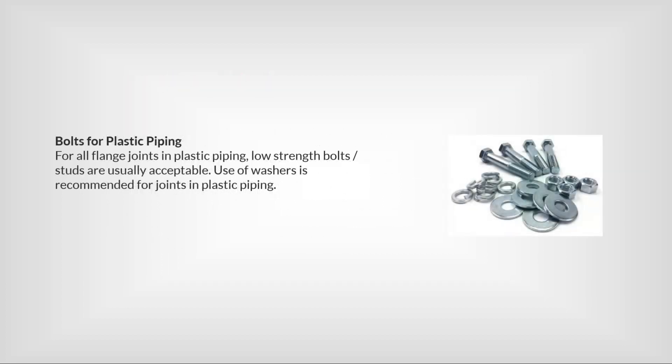For all flange joints in plastic piping, low strength bolts / studs are usually acceptable. The use of washers is recommended for joints in plastic piping.